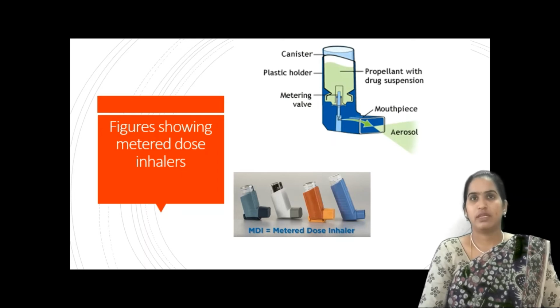So this figure shows the assembly of metered dose inhalers. Here in this canister, the drug will be placed. The canister is held in a plastic holder, and in the canister there is a mixture of propellant and drug in the form of a suspension. There is a metering valve which measures the required amount of dose.